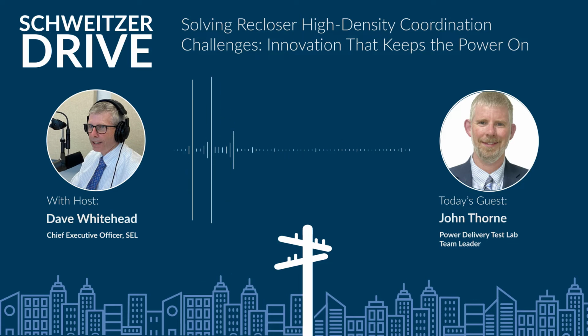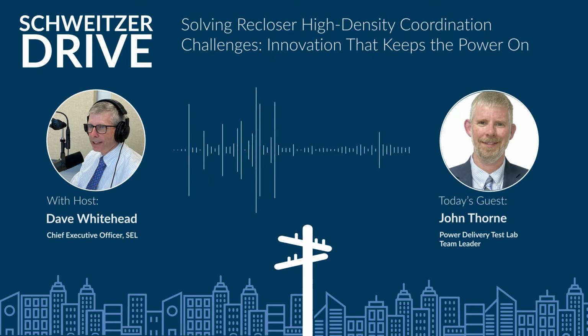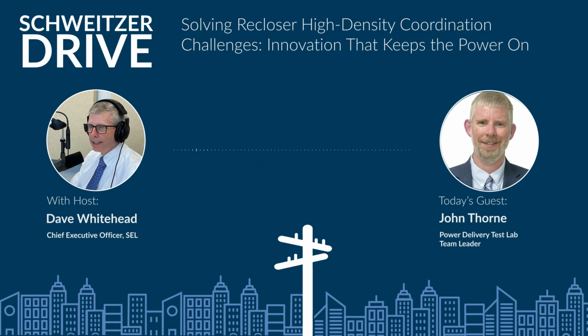It's fairly easy for us to deploy. It works well, but yet it does this amazing thing of tripping the correct device. Because again, step number one in any kind of power system protection is you've got to interrupt the fault. That's number one. We've got to stop the fault current from flowing.